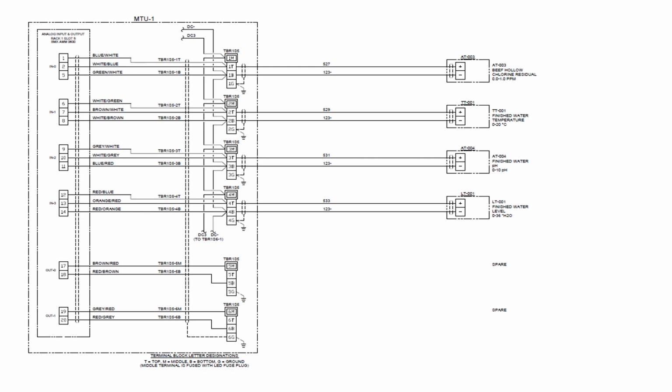So in this case, you can see this bottom one here, we have water level. That's going to be sending somewhere between a 4 and a 20 milliamp signal back to our PLC on one of these wires. One of these wires here is going to be a signal wire. The other one's going to be tied to ground. You can see this bottom one looks like it's our ground wire, and this top one's going to be the actual signal wire. Okay, so that's essentially what's happening in this diagram. In the middle here, you'll see some terminal blocks.